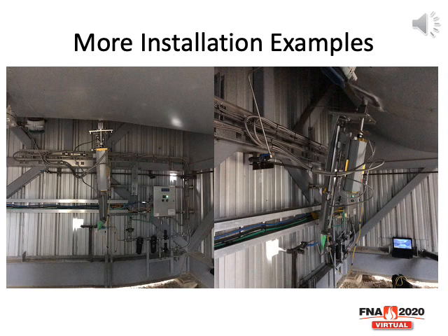You also want to consider where people need to walk around the furnace. And finally, what the temperatures are around the furnace. On the top of the furnace, some furnaces can be very hot, so that's a consideration for the controls that are monitoring the retract and the other sensors. So all these are considerations, and you can see one other thing in this photo, which I haven't mentioned earlier, which is the air system that feeds the camera. There is often cooling air, the pneumatics that operate the retract, and a purge air for the lens.